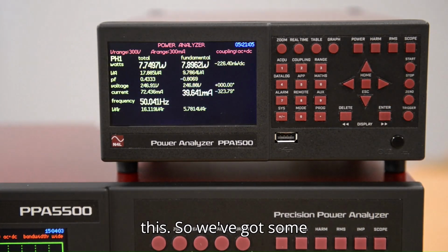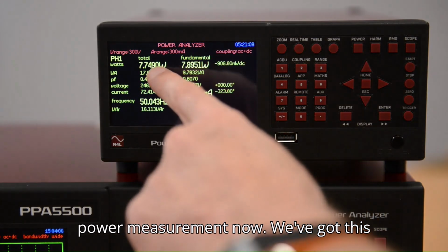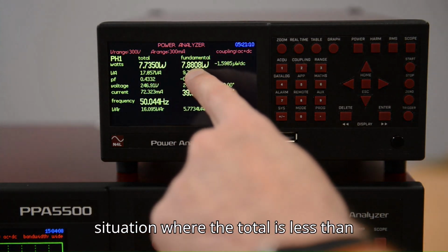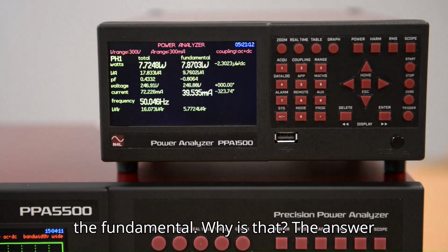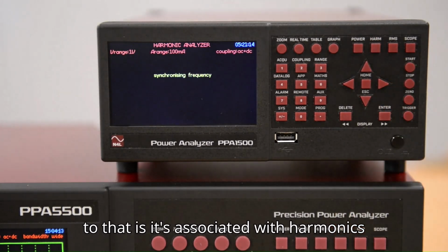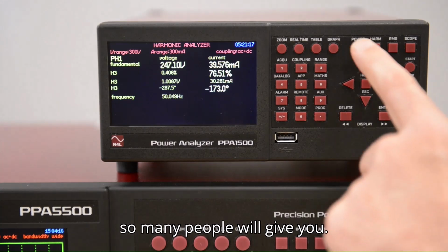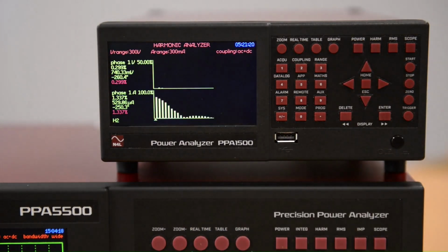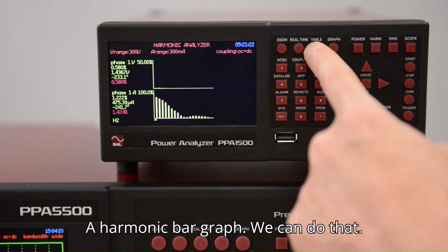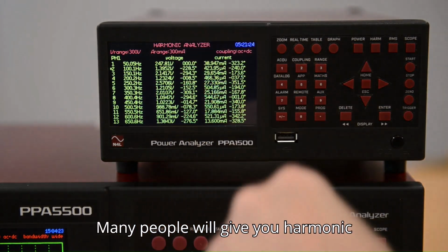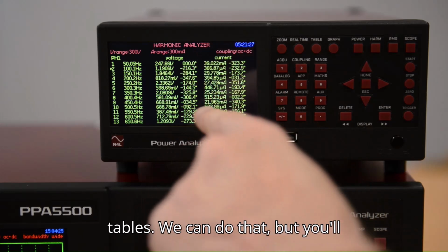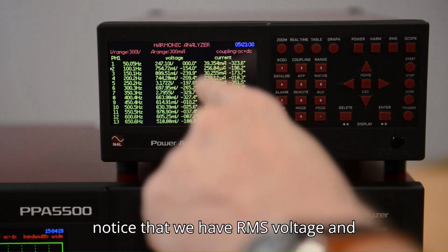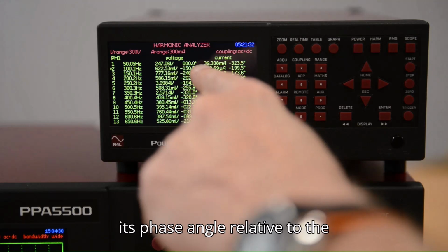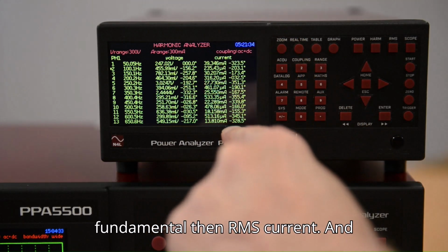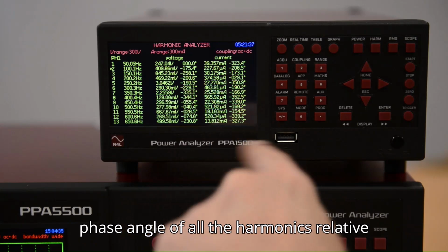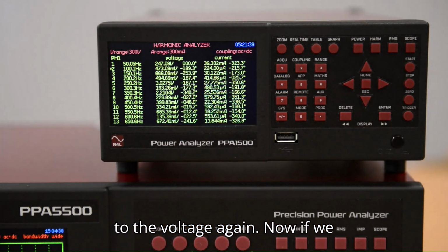So we've got some power measurement now. We've got this situation with a total less than the fundamental. Why is that? The answer to that is it's associated with harmonics. So many people will give you a harmonic bar graph. We can do that. Many people will give you harmonic tables. We can do that. But you'll notice that we have RMS voltage and its phase angle relative to the fundamental, then RMS current and phase angle of all the harmonics relative to the voltage again.